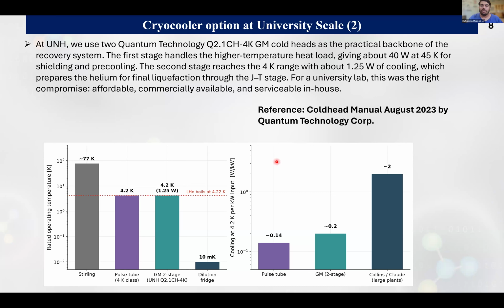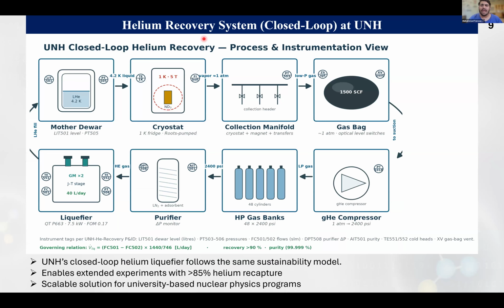This shows how reliable it is at university scale for liquefying gas into liquid. Going back to the schematic from the first slide: we consume helium in our cryostat, capture it through the manifold, compress it into the gas bag, then use compressors to put it into gas cylinders, purify the gas, and send it into the dewar or reservoir. It's a closed loop that helps us conserve helium and maintain our sustainability footprint.